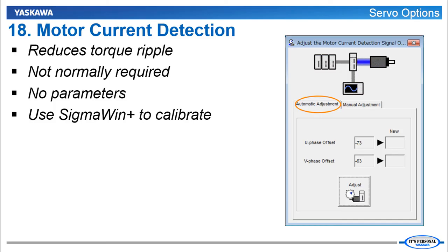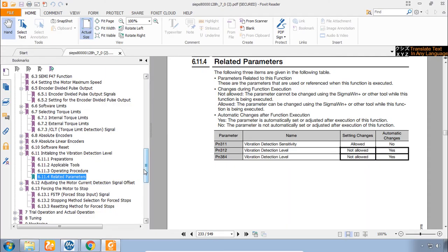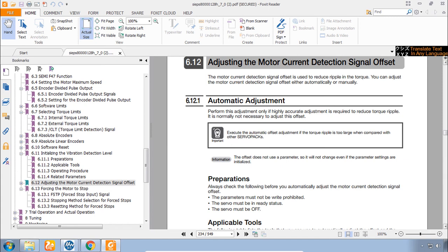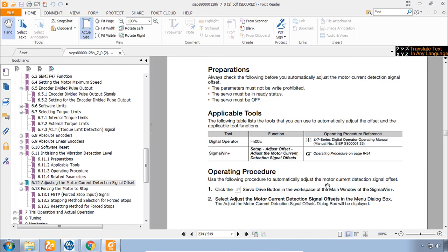And the final option we will discuss is the motor current detection. This is a fine tuning calibration that you can do on the motor to reduce torque ripple. You probably won't see any difference in the operation. It's not normally required. There are really no parameters to adjust and it can only be done through Sigma Win Plus. That's in the next section here of the manual 6.12 adjusting motor current detection signal offset. If you were to do a trace in Sigma Win Plus of the torque signal and you find that it's oscillating rippling. And you find that the ripple is large compared with the other servos. Then you might want to try this before you try to use a tuning to get rid of that torque ripple.